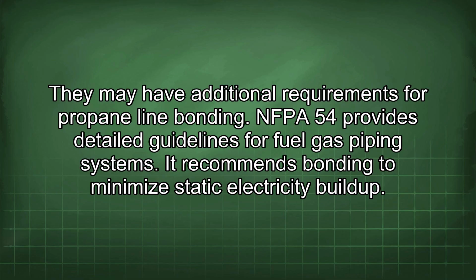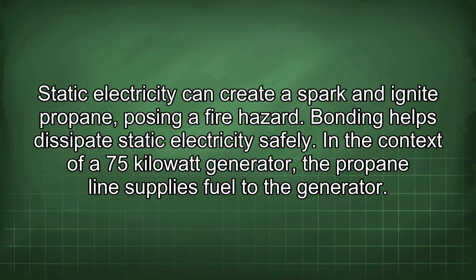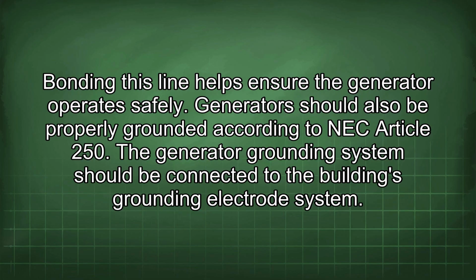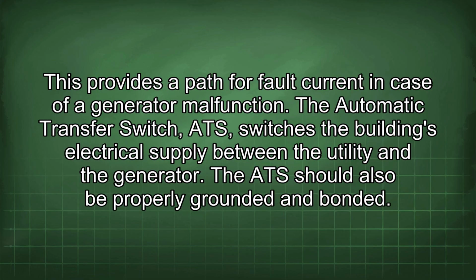NFPA 54 provides detailed guidelines for fuel gas piping systems. It recommends bonding to minimize static electricity buildup. Static electricity can create a spark and ignite propane, posing a fire hazard. Bonding helps dissipate static electricity safely. In the context of a 75 kilowatt generator, the propane line supplies fuel to the generator. Bonding this line helps ensure the generator operates safely. Generators should also be properly grounded according to NEC Article 250. The generator grounding system should be connected to the building's grounding electrode system. This provides a path for fault current in case of a generator malfunction.